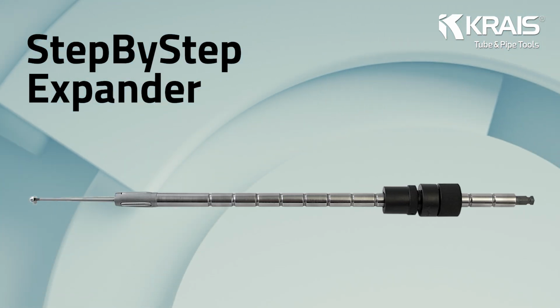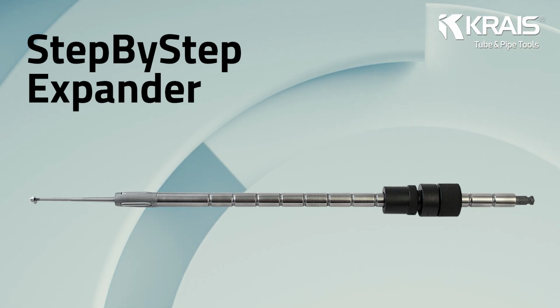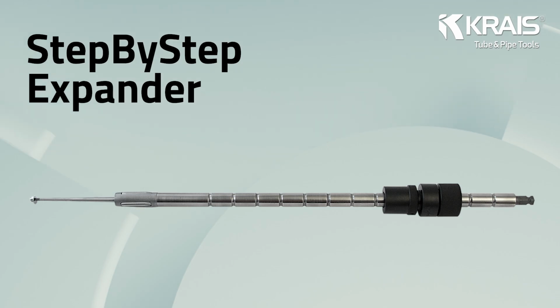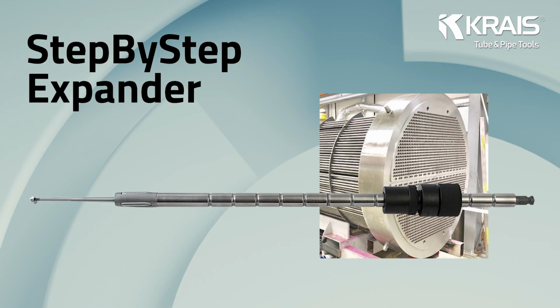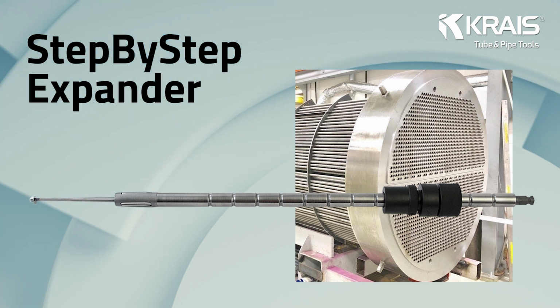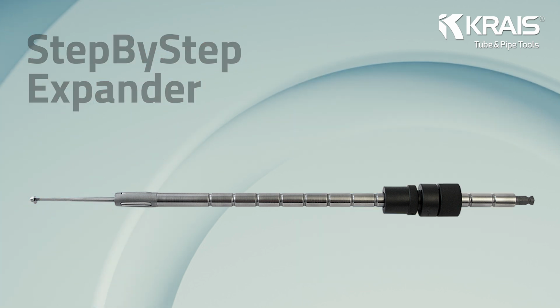KRAIS step-by-step rolling is used for very thick tube sheets. The thrust collar is repositioned along the cage, and rolling is executed in controlled increments. It is applied where tube sheets are exceptionally thick, and repeatability is required while managing process time and forming loads.